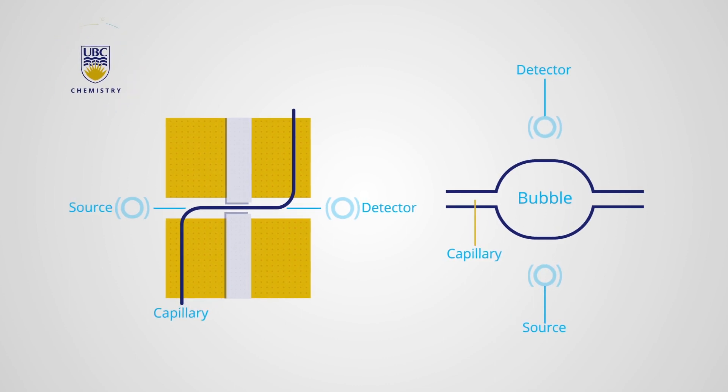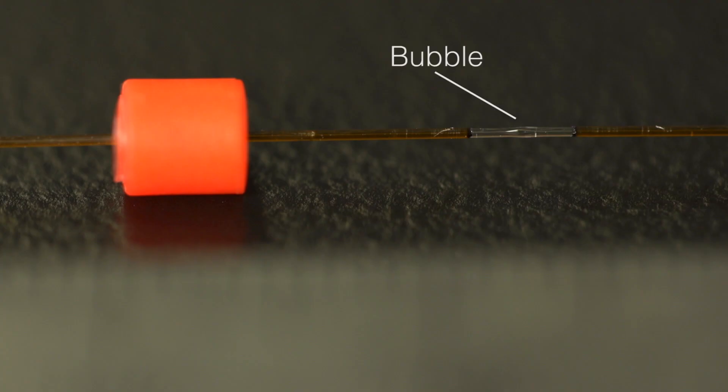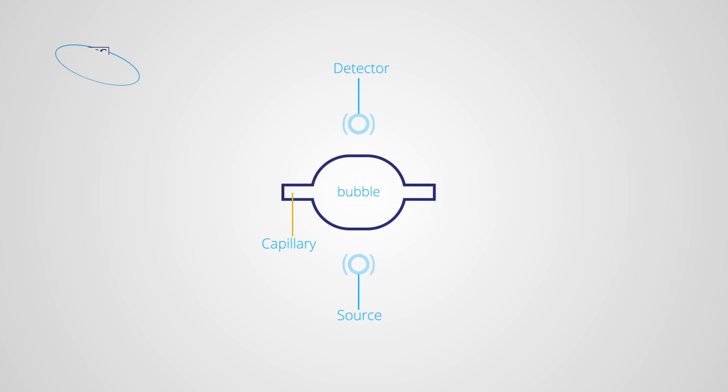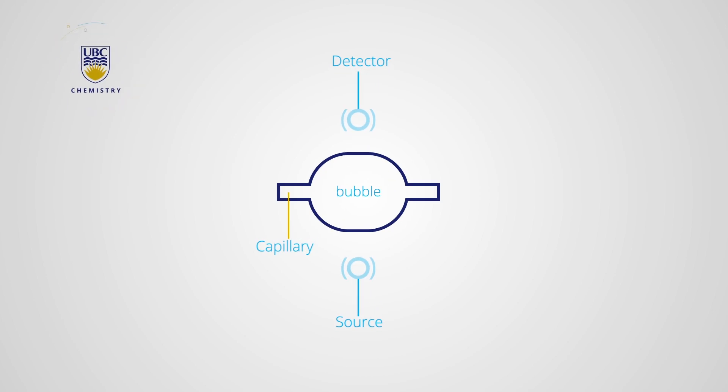Detection of the components occurs on the capillary. This method of detection is used to avoid extra column band broadening. As seen here, a portion of the capillary is isolated and widened slightly to allow light from the light source to pass through it and reach the detector. This widening improves the detection sensitivity since the path length of the capillary is increased.